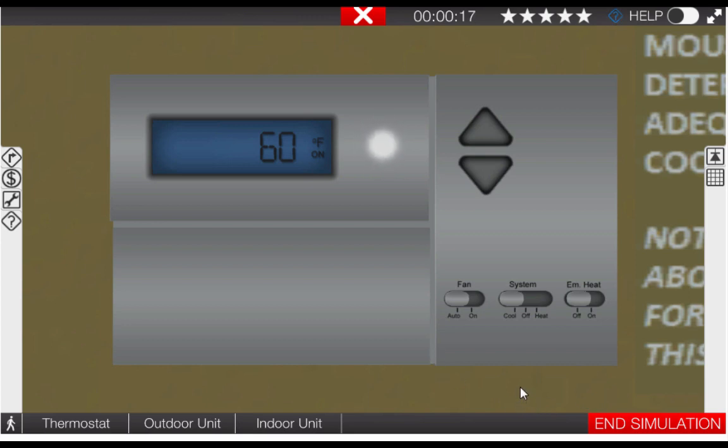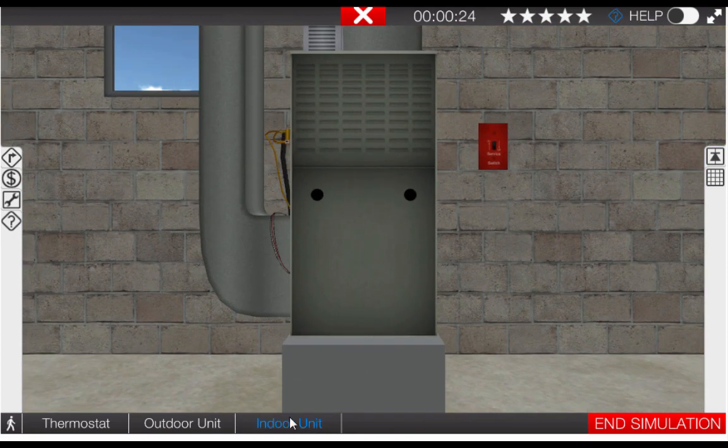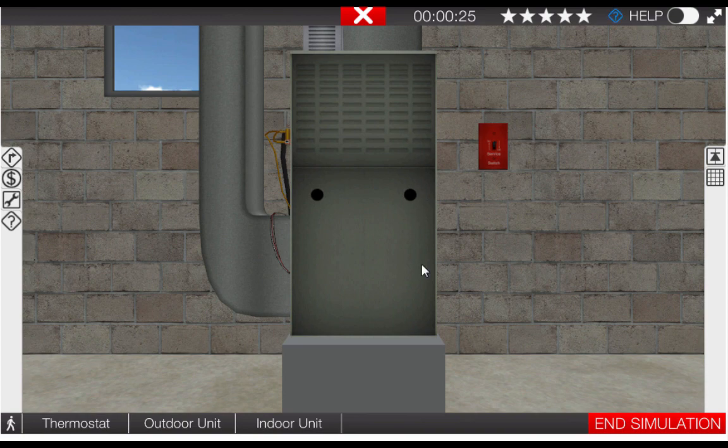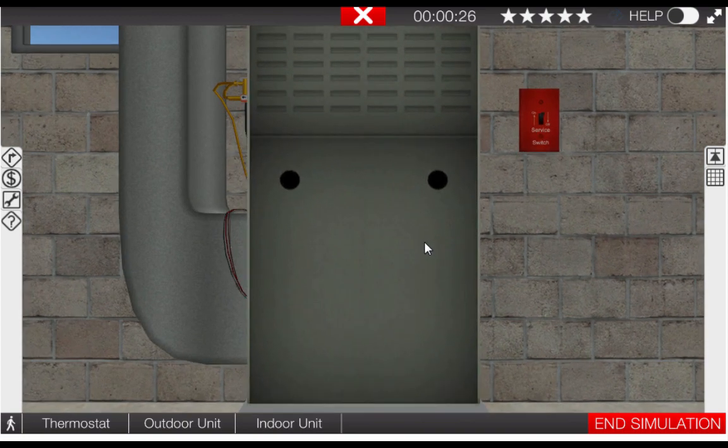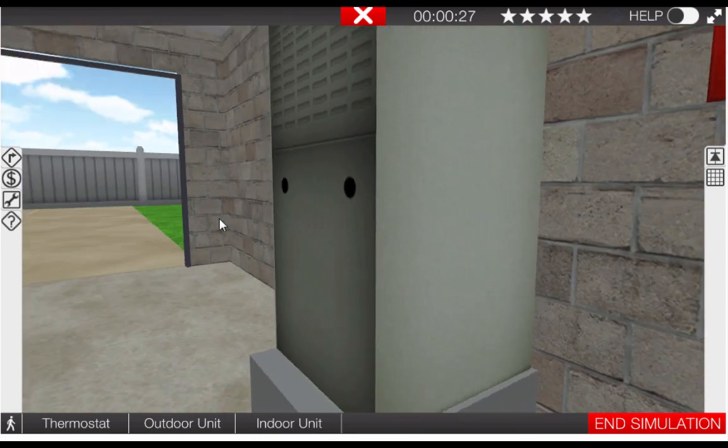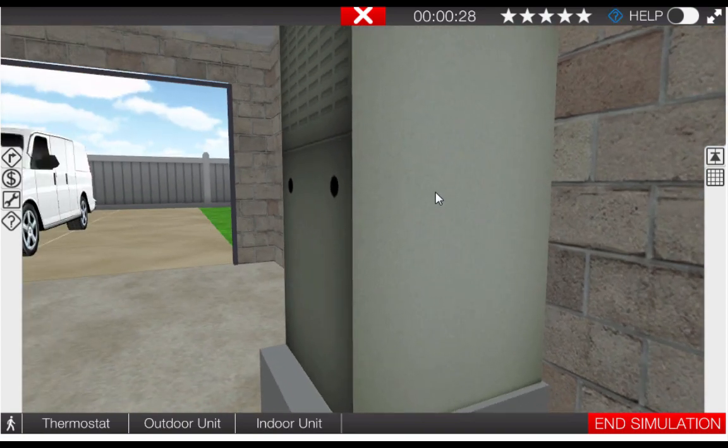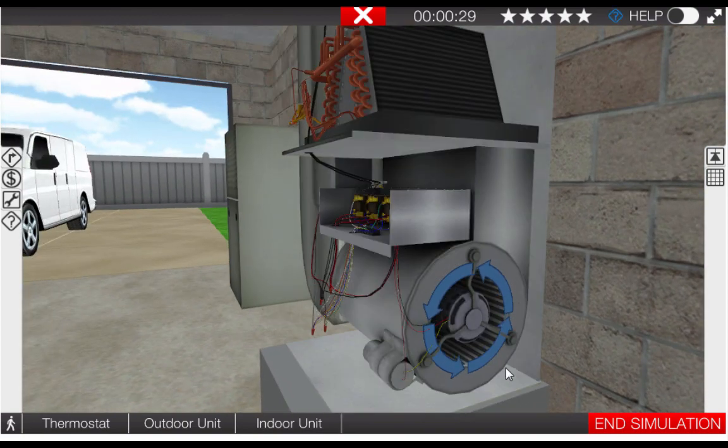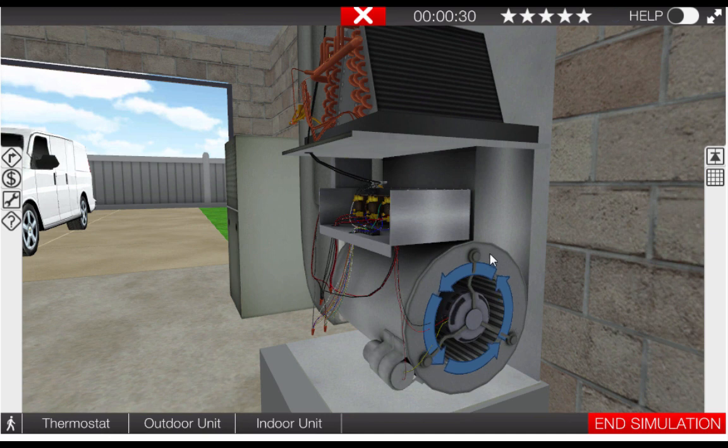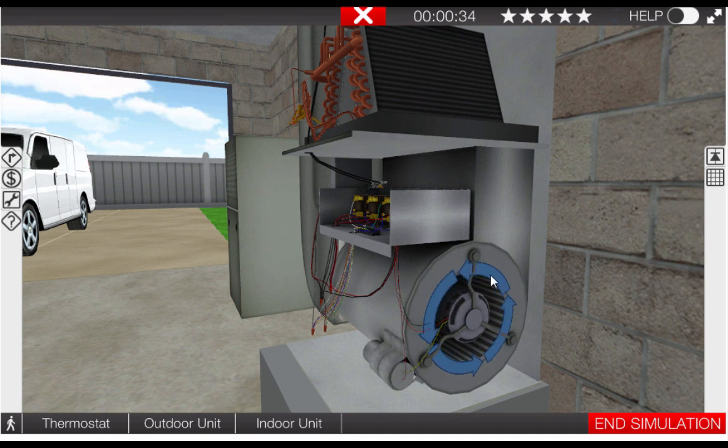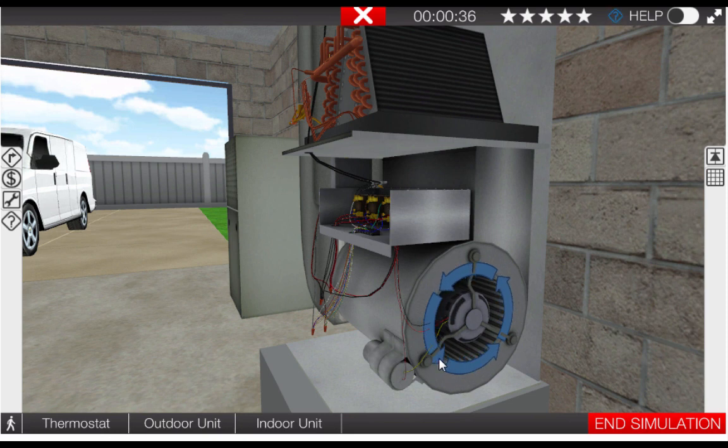Next we want to take a brief inventory of what electrical loads are operational starting at the indoor unit. Click the indoor unit icon. If you can't hear the blower motor running you can always remove the cover and observe the graphic on the indoor blower motor. We can see here that in fact the indoor blower or indoor fan motor is operating.